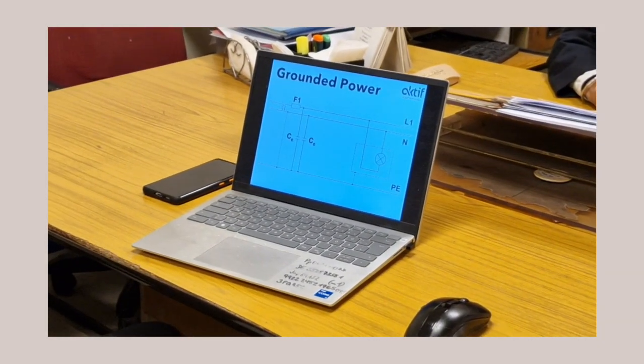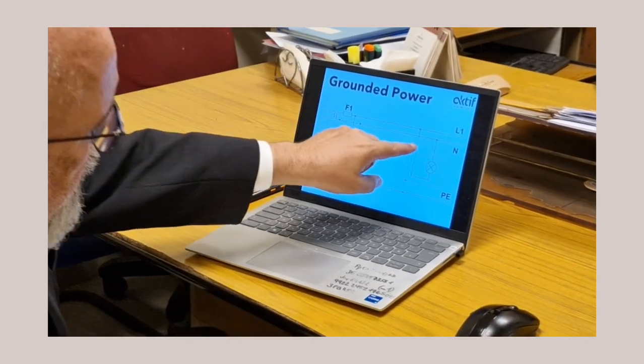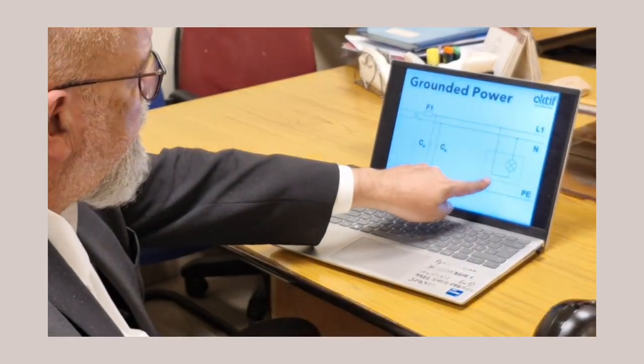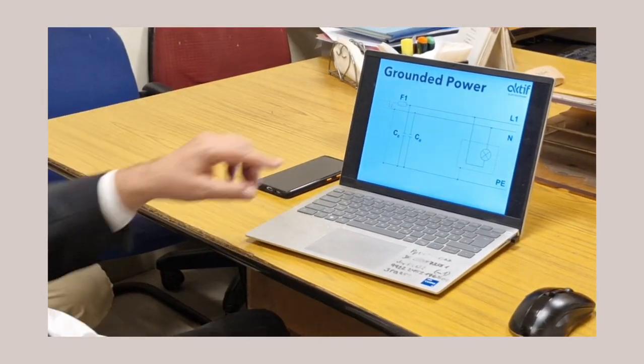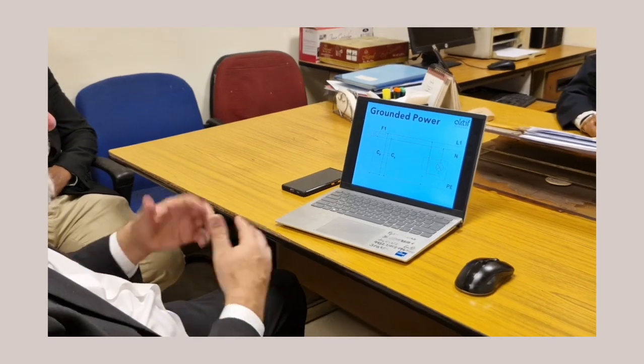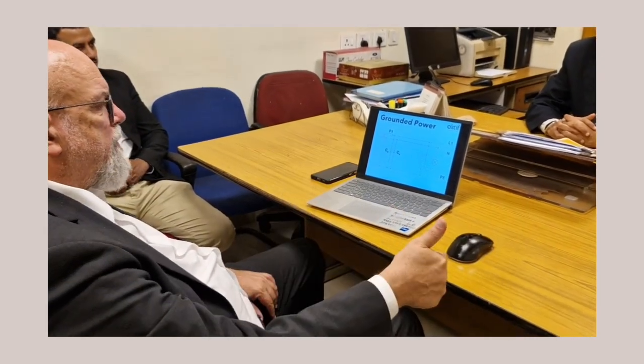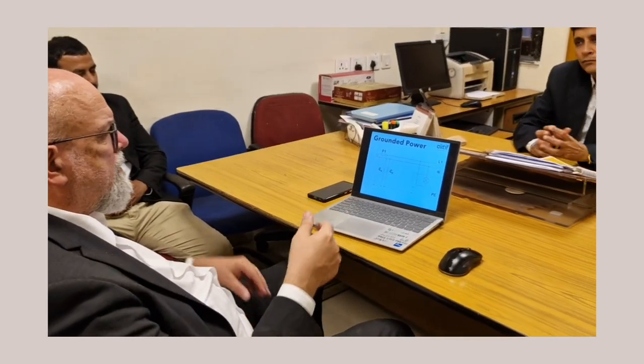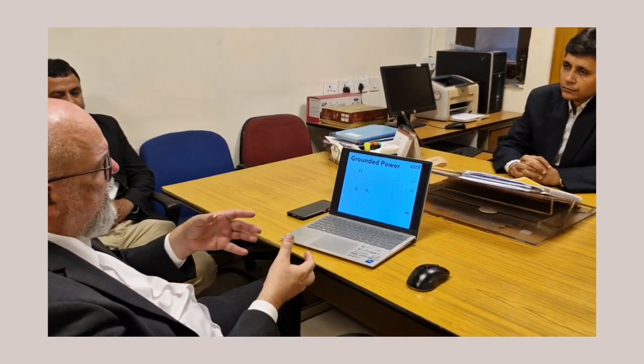The main problem is that when you are lying on the operating theater table or in the bed in the intensive care unit and the power shuts down, you're dead. That is the main problem. To avoid this, instead of grounded power, where you have a connection between the secondary side of the supplying transformer and ground, a potential fault at the housing of medical electrical equipment can directly connect to the line and cause a dramatic fault. In this case, the fuse will trip and the system is down. No more life support, no more light for the operation, no more support for the electrical equipment the surgeon is using.